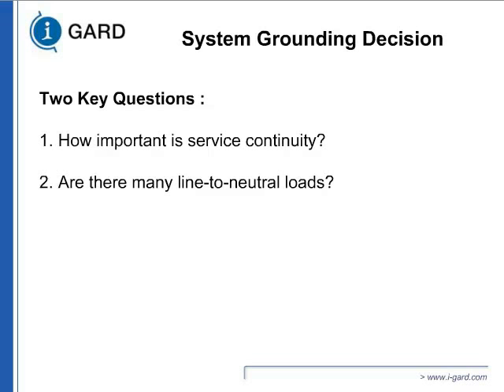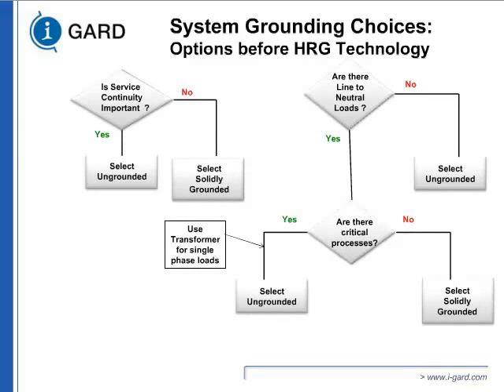Before the high-resistance grounding technology came in, when I was in the plant engineering and doing the plant work, you only had very few options. You went through this chart and you decided if the system grounding continuity is important, I'm going to go to ungrounded, strictly ungrounded. If it's not, okay, I'm going to go solid grounded, because solid grounded essentially will take you down in the first fault. Then we ask, are there any line to neutral loads? Because an ungrounded system normally has three-phase, 3 wires and does not supply your neutral load. If the neutral loads are needed, then you select basically solid grounded system. If they are not needed, you select the ungrounded system.